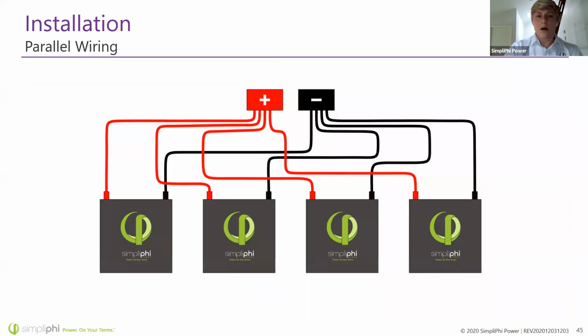For wiring, make sure you wire all positive terminals to a positive bus point, and the same with all negative terminals. You'll also want to use the same gauge and same length wire on each battery — so if one run is 4 feet, the other run should also be 4 feet. The minimum gauge you can use is 6, but I've seen almost everybody use 2 gauge or larger.